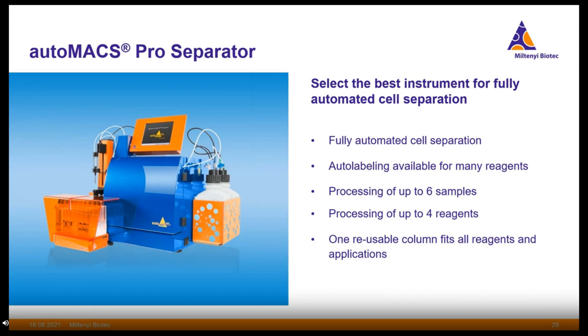The second instrument is the AutoMACS Pro Separator, which performs cell separation fully automated — including auto-labeling by adding microbeads to samples, then incubating and separating. Up to six samples can be separated in one run. This instrument uses a reusable column that can be used for up to two weeks, which is of interest for users performing many cell separations.